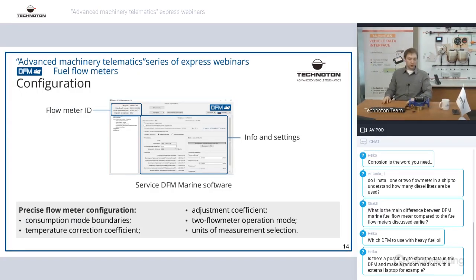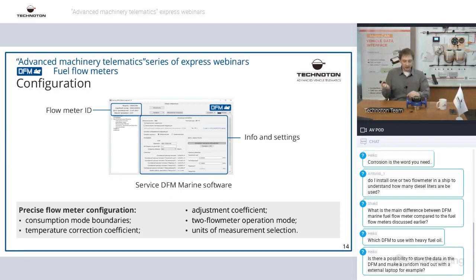Any flow meter with an interface is configurable. So using service kit S6 or service kit DFM, we can easily access the brain of the DFM flow meter and check different settings. We can adjust flow rate ranges for detecting idle mode, nominal mode, and overload mode.